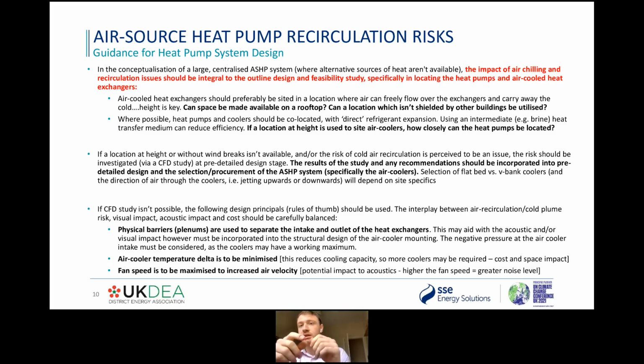But you've also got to consider the impact on acoustic performance. The faster the fans, the lower the air recirculation issues, but the higher the noise levels. That's something we've seen on this project - having to balance acoustics, visual impact, and air recirculation quite finely.